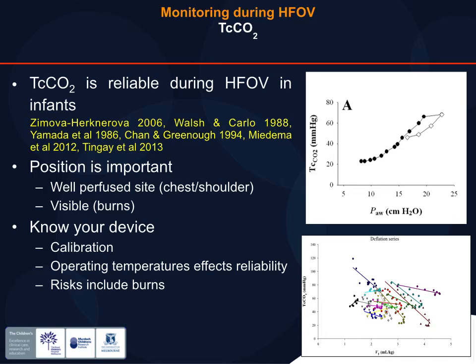But this is a slide out of my PhD, which you probably can't see, most of you, where we looked at tidal volume measured in mL per kilo during high frequency, and TCO2 measurements for a series of babies. And what we would hope is the TCO2 and the tidal volume measures would correlate well, because that's essentially what we're trying to get, isn't it? CO2 clearance is dependent on tidal volume and rate. And we saw in many babies there was an appropriate correlation, but in a couple of babies it didn't do what we expected it to do. So that means that one of these two measures, because neither of them are the gold standard, weren't working. So just be aware it won't work in every baby, and the trend is more important.